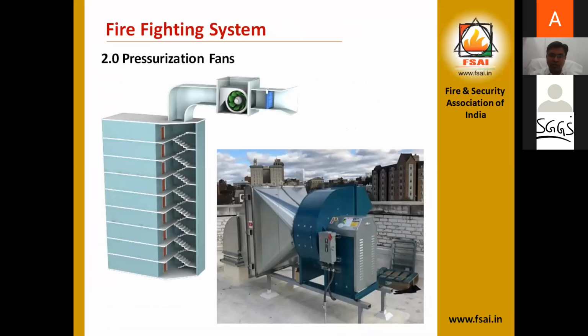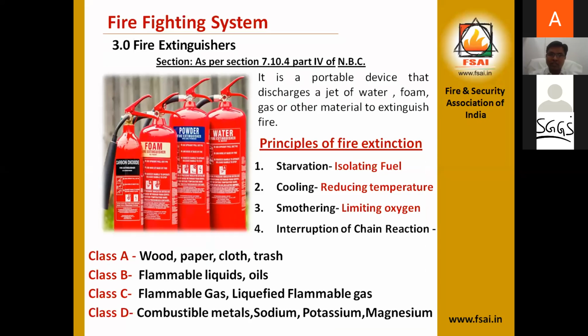The next is the fire extinguishers. As per section 7.10.4 part 4 of NBC, it is a portable device that discharges a jet of water, foam, gas or another material to extinguish the fire. To extinguish the fire means to stop the fire. So there are a total of 4 principles of fire extinction. The first is starvation. Starvation means isolating the fuel from burning.